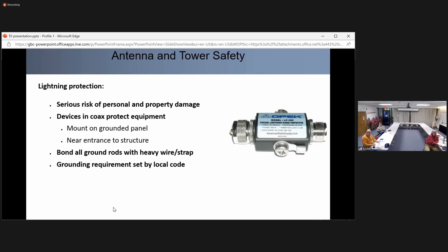So, towers need to be grounded. Again, they're basically a huge lightning rod. And the proper way for grounding them, as dictated by most safety rules, is that for each leg of your tower, most towers have 3 legs, you'll drive a separate 8-foot ground rod in near the base of the tower, near each leg. So there's a separate 8-foot rod for each leg. Those are all bonded, or connected to each other and the tower. So the tower is connected to each of the three rods. The three rods are connected to each other.